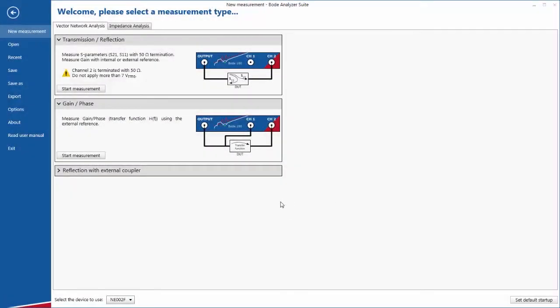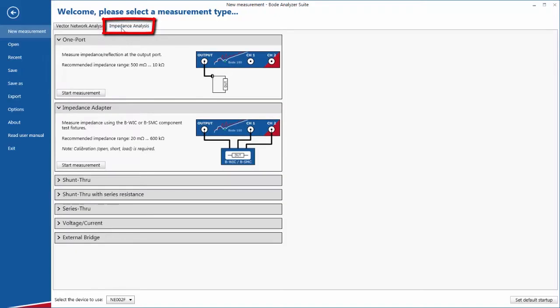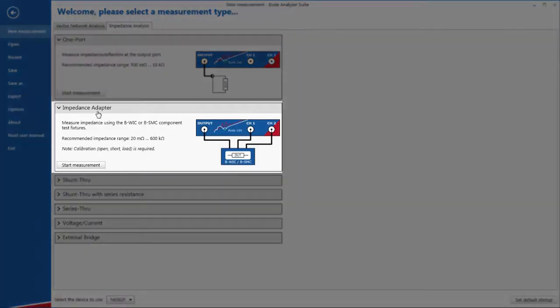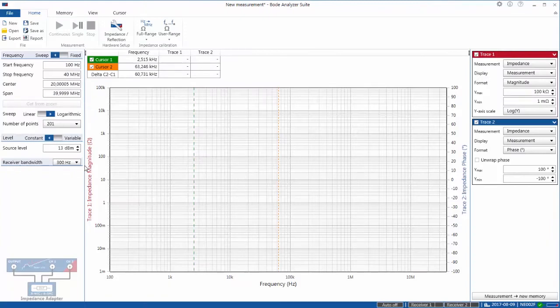When you run Bode Analyzer Suite at first, you will get a screen like this. This is the opening screen, and we are doing impedance analysis, so first thing that you need to do is click on this tab here, and then you see several options. We are using an impedance adapter, which is this box here, and therefore all you have to do is click on this, and this will automatically set up the Bode for the use of the impedance adapter.